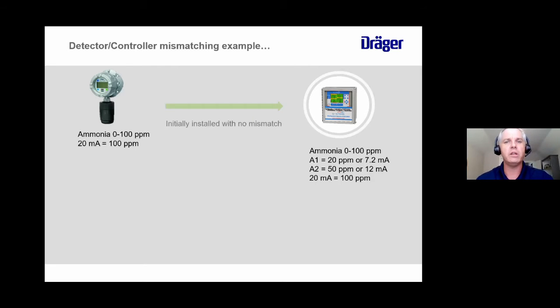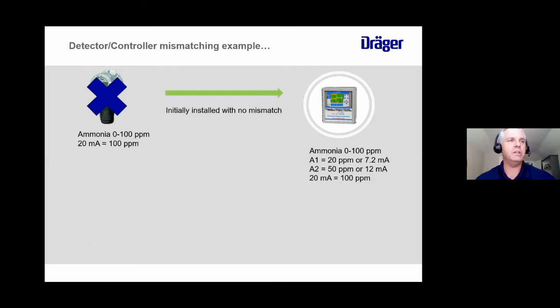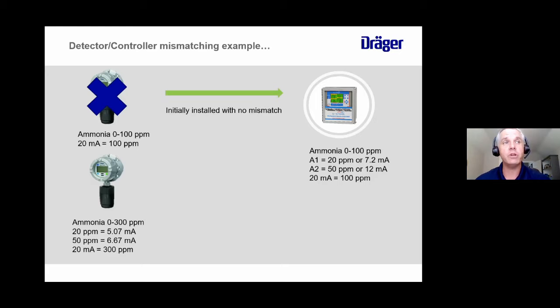Then all of a sudden, lightning strikes, or something happens to the transmitter, and you lose your transmitter. So you call Don Johns down in Mobile. Hey, Don, lightning hit my transmitter. I need a new transmitter. So we get you a new transmitter. And what comes from the factory is that transmitter with the range defaulted for that sensor being 0 to 300 ppm. Now we've got a problem because we forgot to go back and change the range on the transmitter to be 0 to 100.